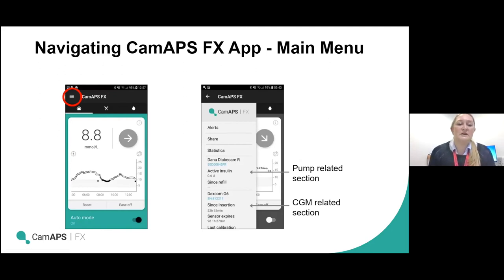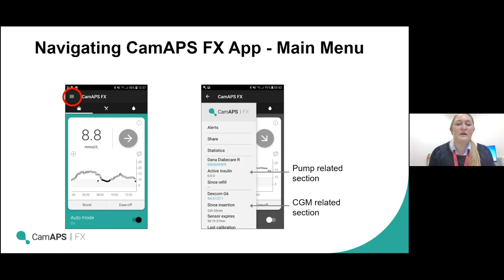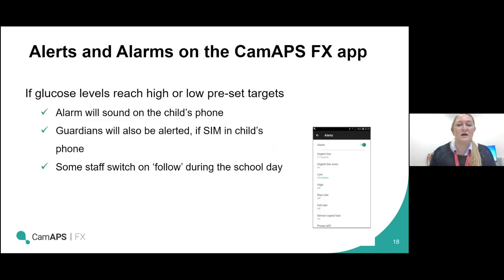On the home screen, the three lines at the top left take you to an additional drop-down menu. The things that are good to know are the very top two: the alert menu and the shares menu. The alert menu has the sensor app embedded within the closed loop app, meaning all the usual alerts and alarms from a continuous glucose monitoring system can be set within the app. Most children will have alerts and alarms preset by parents at different levels relative to what they require.